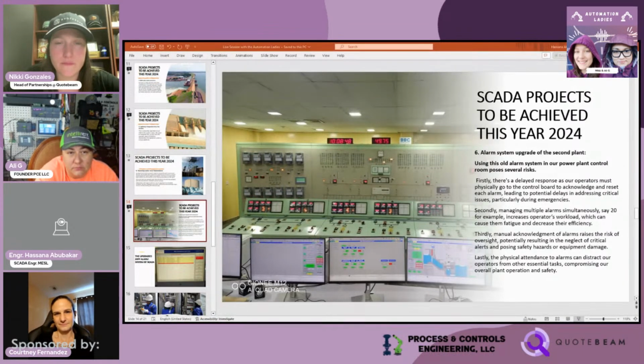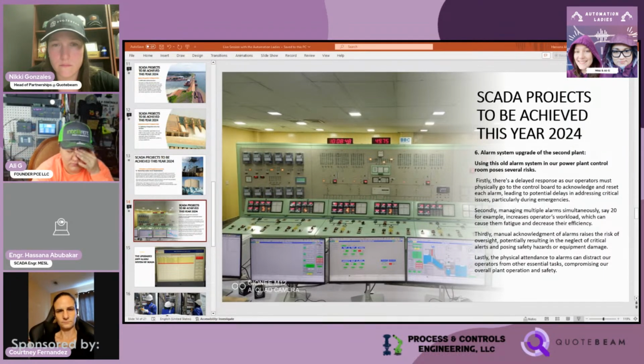Using this old alarm system, which we can see in this picture of our power plant control room, poses several risks. Firstly, there's a delayed response, as our operators must physically go to the control board to acknowledge and reset each alarm. This can lead to potential delays in addressing critical issues, particularly during emergencies. Secondly, managing multiple alarms simultaneously, say 20 for example, increases our operators' workload, which can cause fatigue and decrease efficiency. Thirdly, manual acknowledgement of alarms raises the risk of oversight, potentially resulting in neglect of critical alerts and posing safety hazards or equipment damage. And lastly, physical attendance to alarms can distract operators from other essential tasks, compromising overall plant operation and safety.